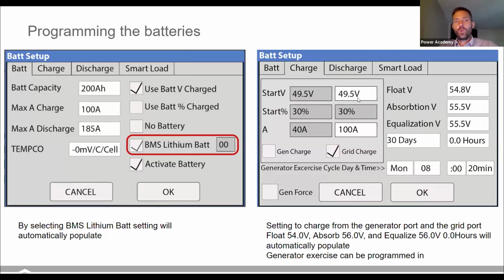Or if you've got the voltage box checked on the left, you could set the voltage at which you want it to start. Under the float and absorption, we float at 54 volts. We absorb up to 56 volts. So that does constant current charging until the battery hits 56 volts, and then it just does constant voltage.